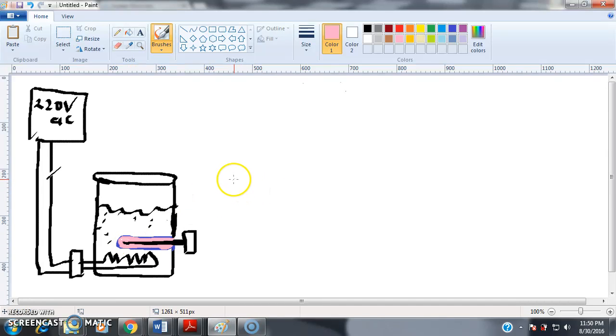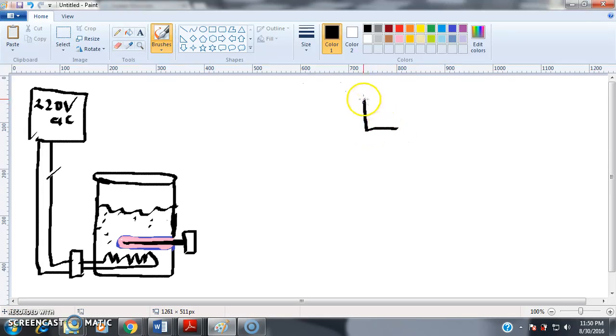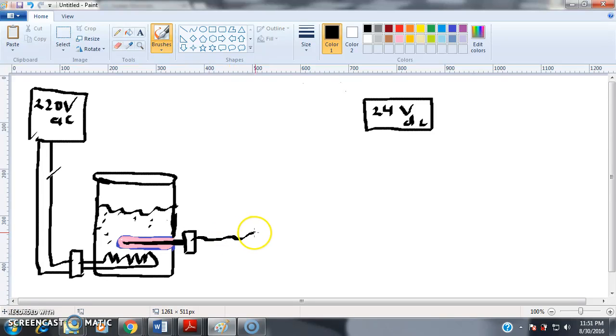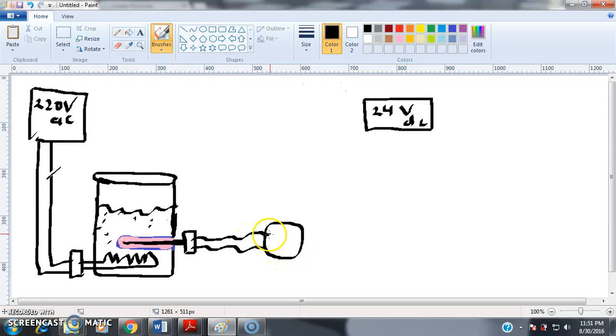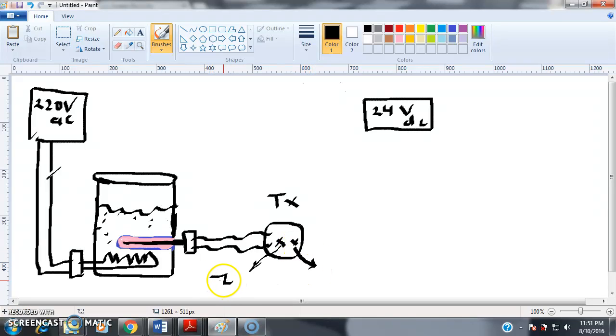On the wiring side, we need a 24-volt DC power supply — not AC. The RTD has two wires. Before connecting to the 24-volt power supply, there is a device called a transmitter. On the transmitter we have two small calibration pins: one is known as Zero and the other is your Span.